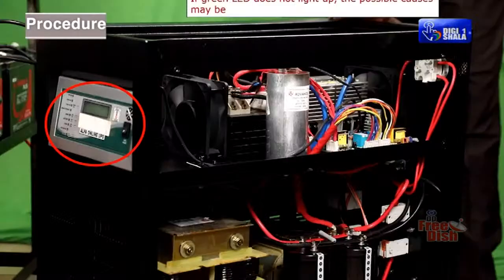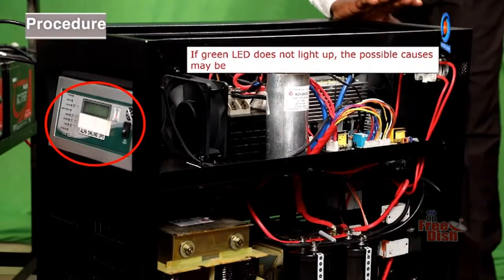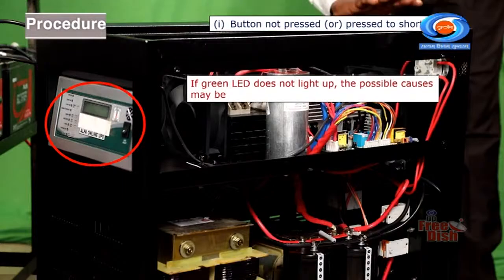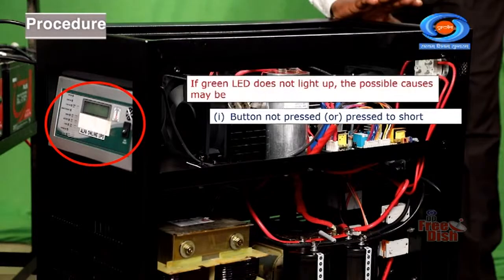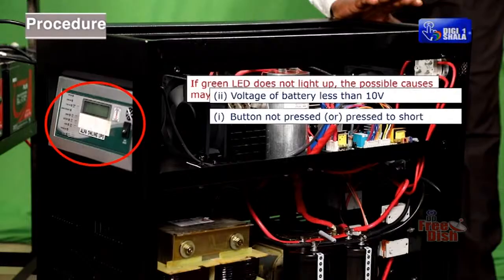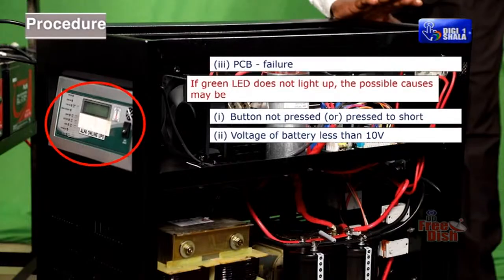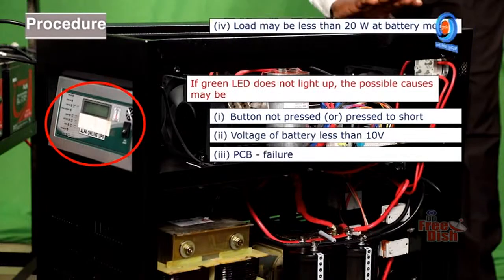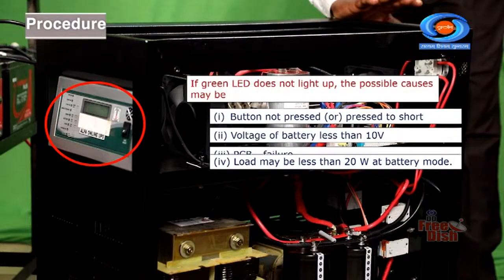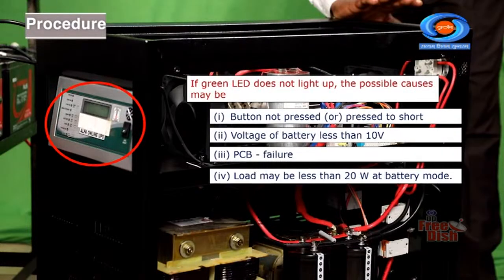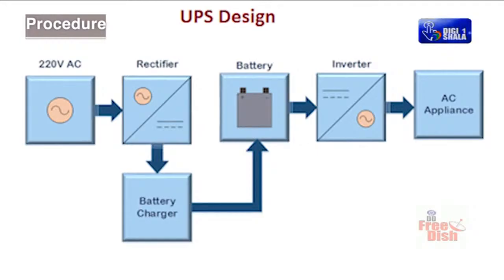If the green LED does not light up, the possible causes may be the button not pressed or pressed too short, battery voltage less than 10 volts, PCB failure, or load less than 20 watts in battery mode. Identify the problem by self-testing the UPS and rectify this fault by referring to the troubleshooting sequence block diagram.